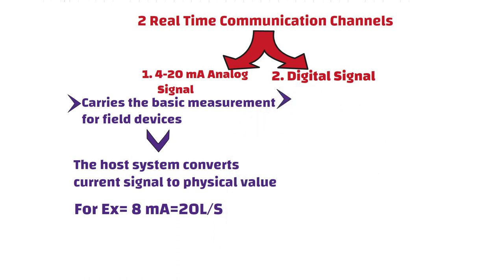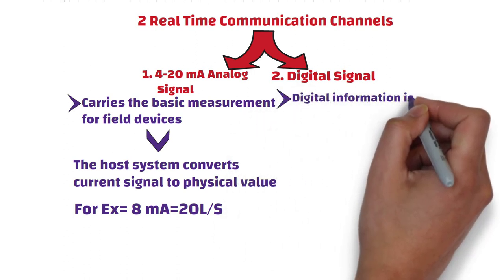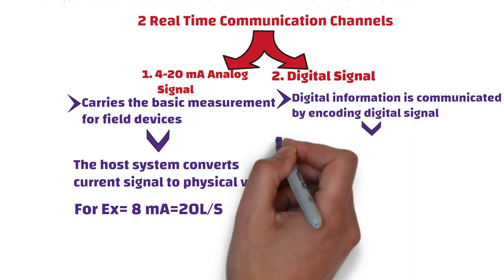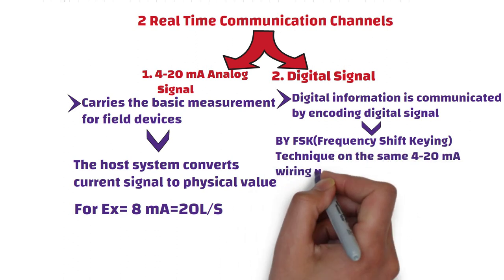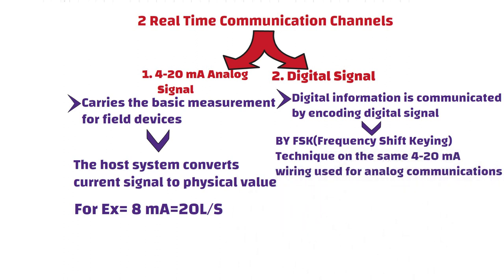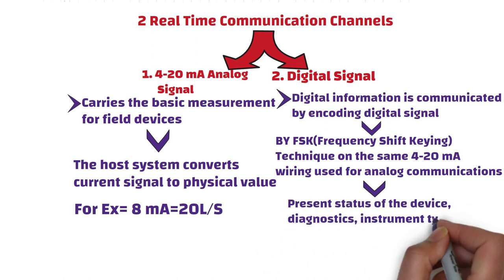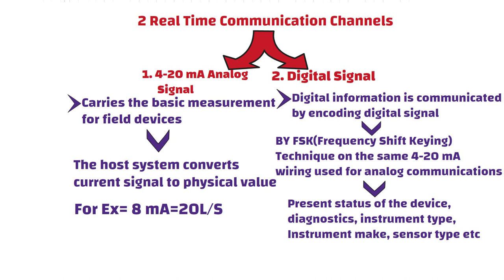On the other side, digital information is communicated by encoding digital signal. And this is done by using frequency shift keying technique on the same 4-20 mA wiring used for analog communications. The digital signal provides different types of information about the instruments, such as present status of the device, diagnostics, instrument type, instrument make, sensor type, model number, etc.